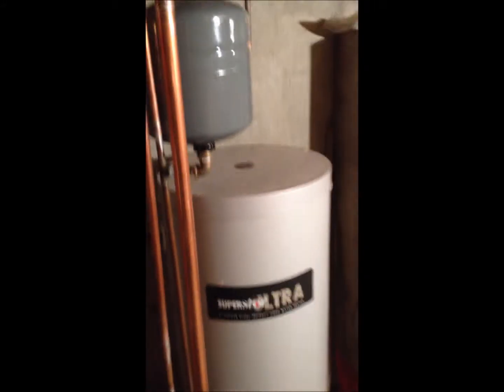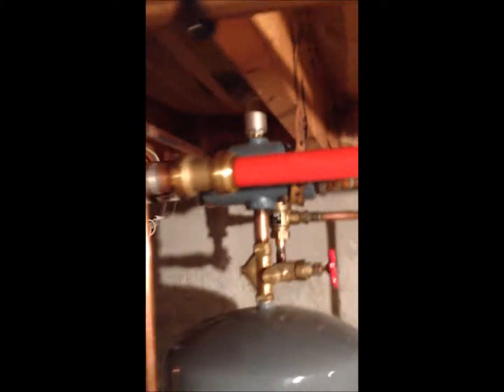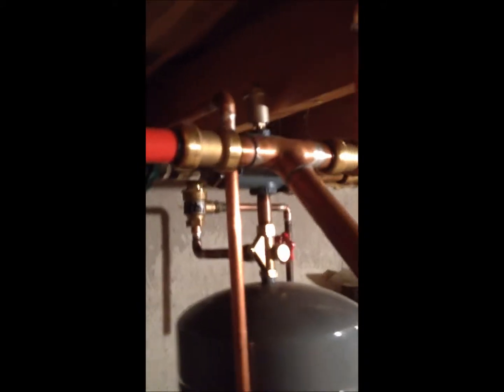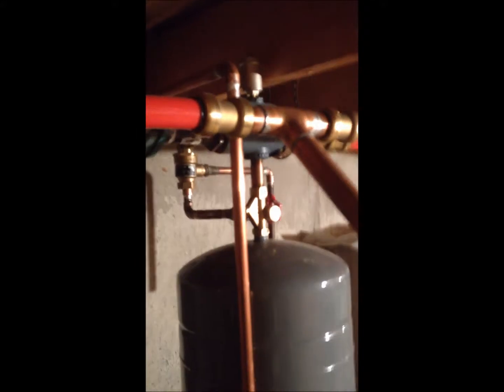The radiators all cost between $50 and $100 a piece, a couple of them a little cheaper. I've got some labor in it, but the parts are probably a thousand bucks total over a two, three year period of collecting. I know nobody really likes these SharkBite connectors I get at Lowe's, but I've never had any trouble with them — except when the boiler got too hot and boiled, and they melted. They won't take boiling water or steam. But they don't leak and you can take them apart. If you screw them up, just save the packages and Lowe's will take them back — just cry the blues and they'll swap them out. I save all my packages for my SharkBites just in case.